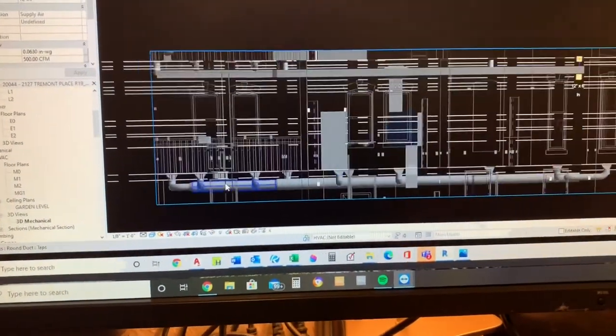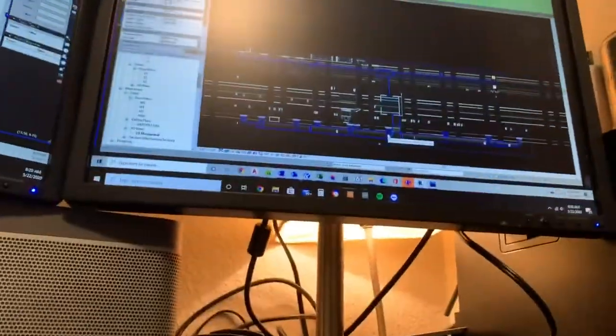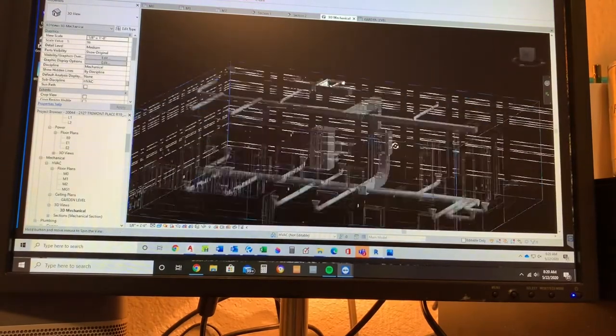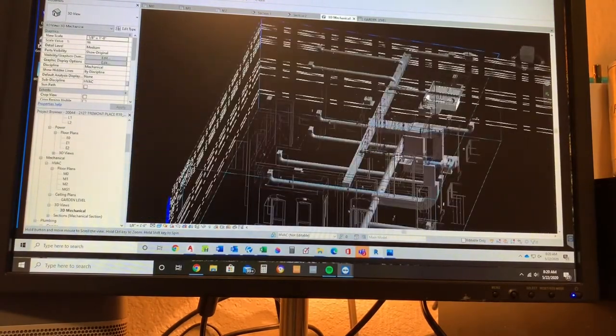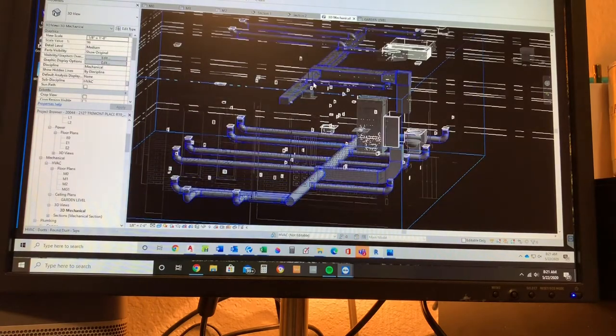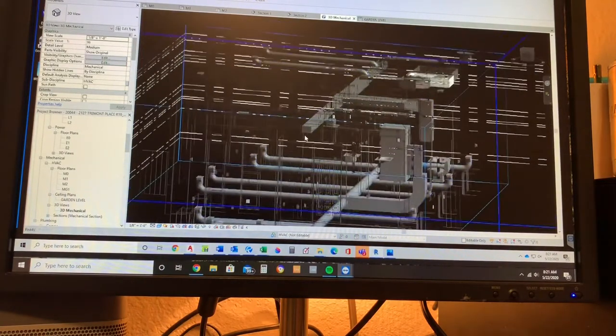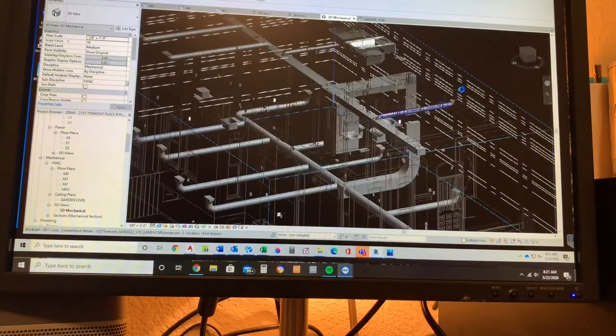I'm going to show you here in 3D what we've got going on — a little 3D section view. This one's a little hard to discern, but you can see the gray is our current underfloor ductwork on the main level. Let me spin this around so you can see it. Here's the 3D view — we're going to do a four-ton cooling system to serve the upper level, which is going to supply up there, and then we're going to provide underfloor distribution. We'll have to carve out a new soffit that's going to be concealed, at a minimum 9-inch drop, so we don't want to alter the historic-looking ceiling.